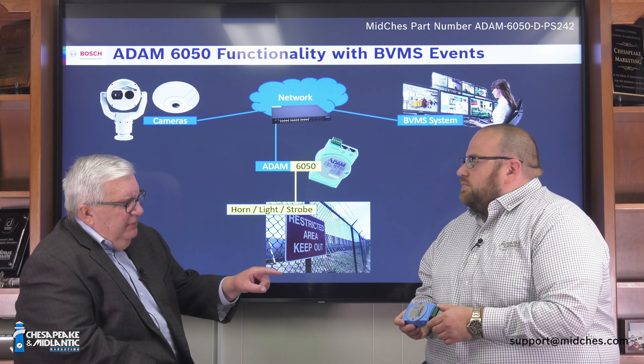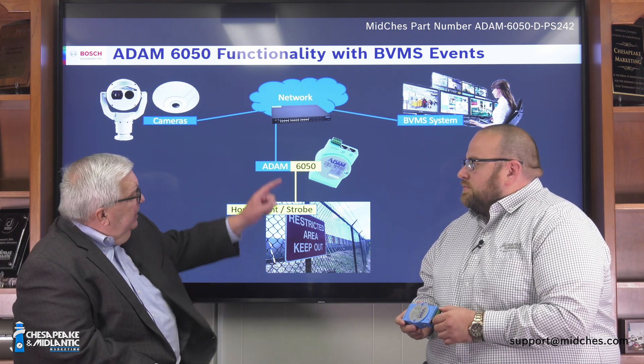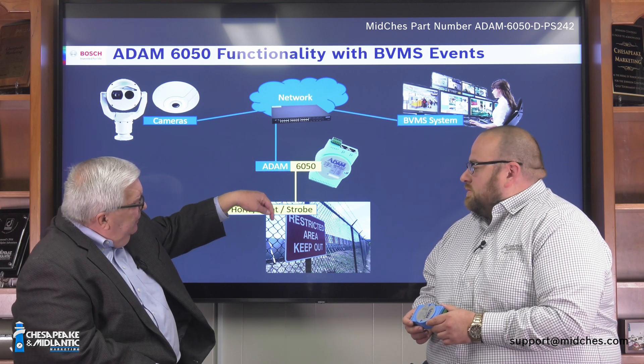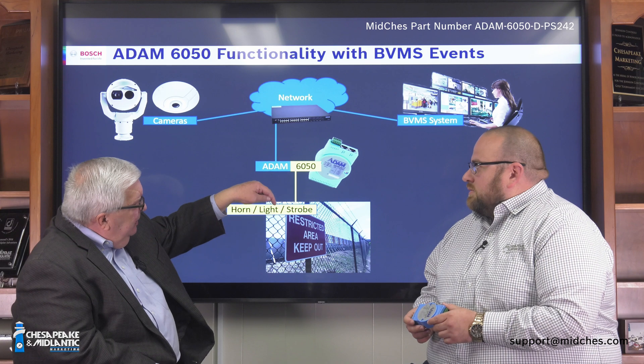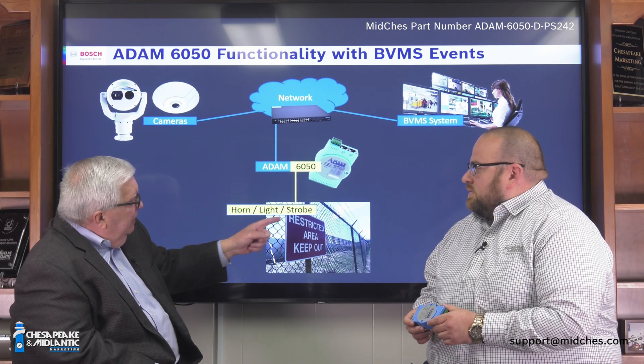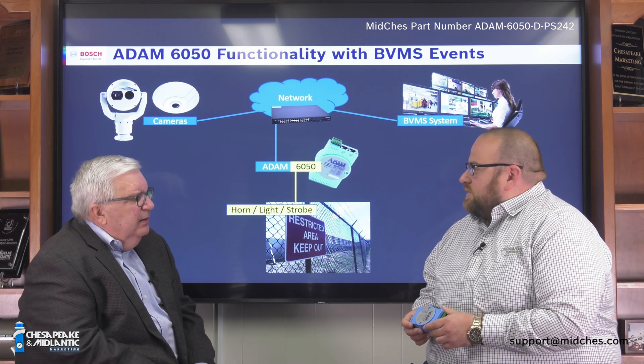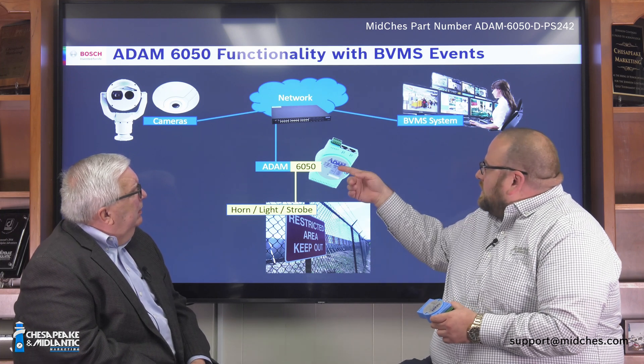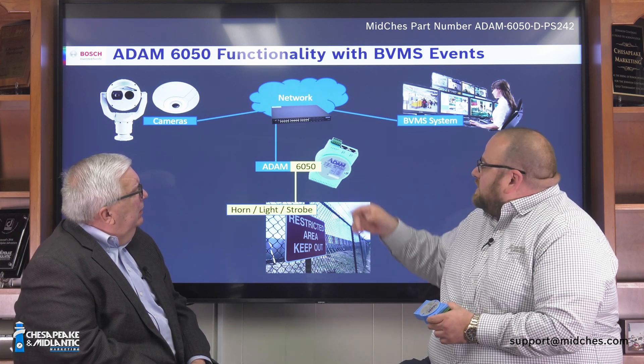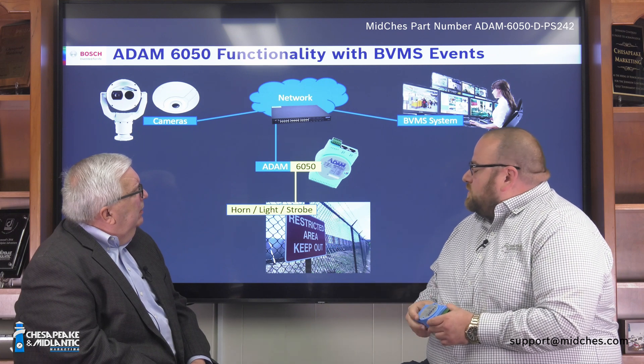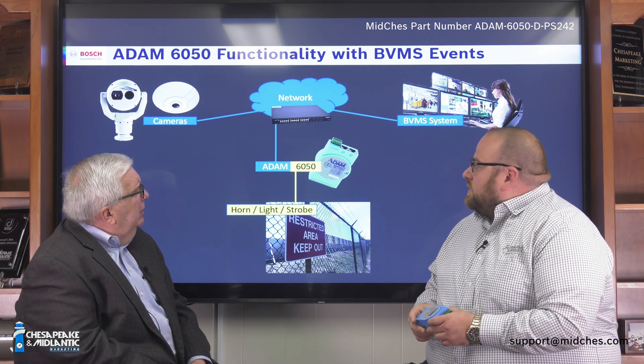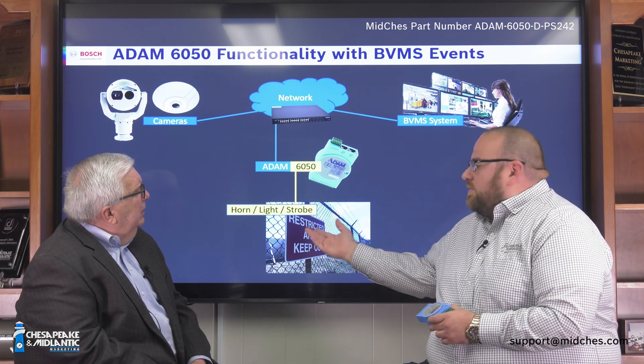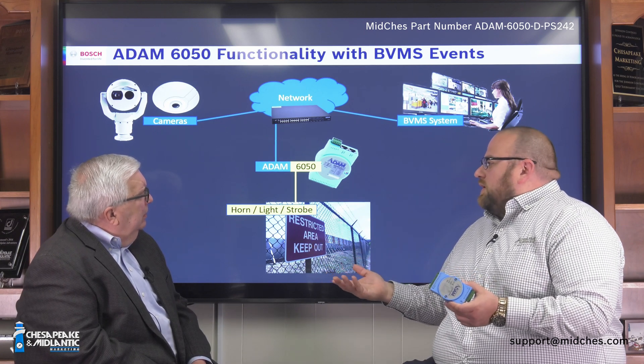This ADAM device is actually over Ethernet, but then comes out to a hardwired connection to a device like a horn or a light or something like that. That's exactly right. Everything else on the system is going to be Ethernet-based, signified by our blue lines here. And then our yellow line here is an actual physical two-conductor cable that would be leaving the ADAM to whatever the customer would need on the other side.